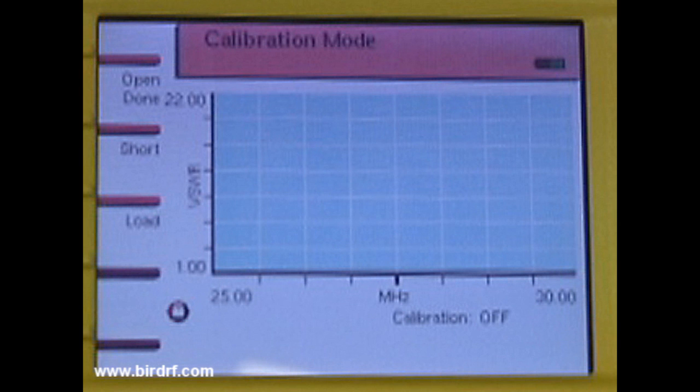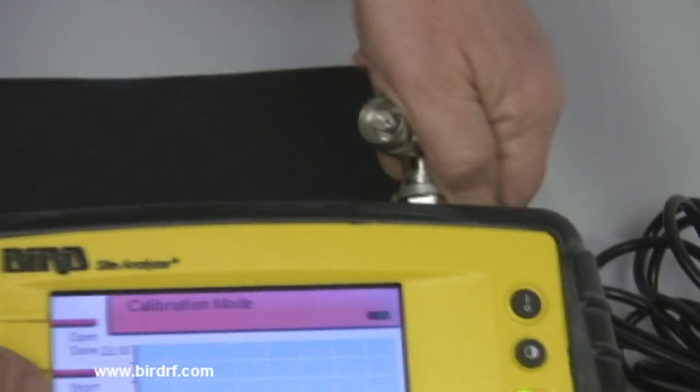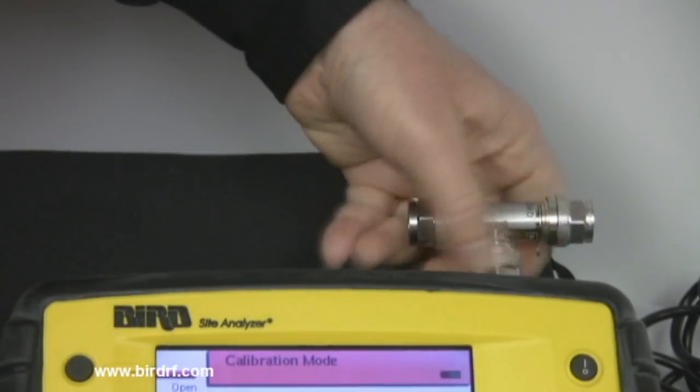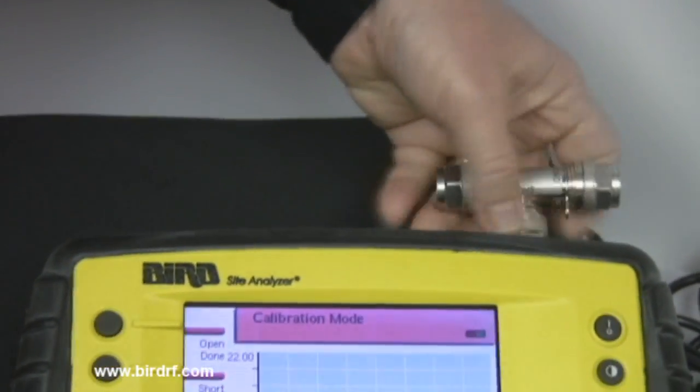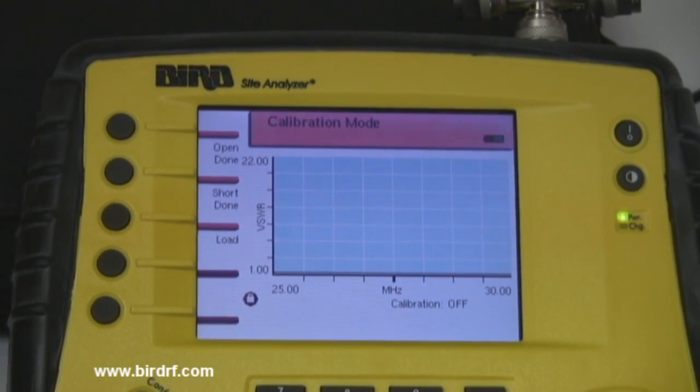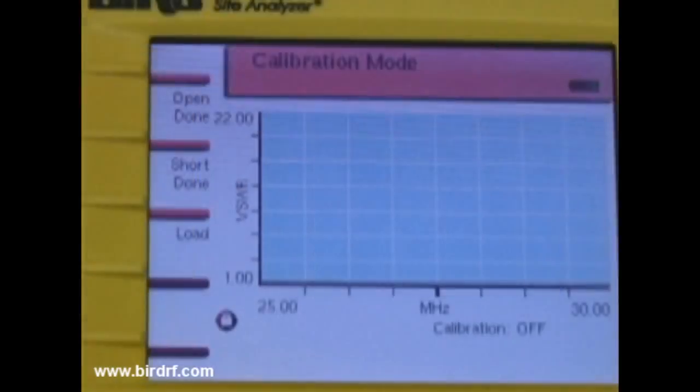Step two is to make the short calibration. Remove the cal combo from the SA and reconnect using the short connector located in the middle of the cal. Then press the short button which is located under the open button on the left hand side of the screen. Wait for the done indication. Again, this is the notification that the calibration using the short has been completed.